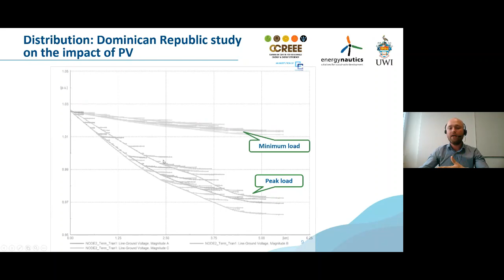When you integrate renewable energy or distributed energy, such as PV power plants, on such a feeder, you will have a declining voltage profile during peak load. You usually have a high voltage set point at the high voltage to medium voltage transformer, and over time, during minimum load, this voltage profile will not decrease as much. Even with some PV penetration, you can get a reverse power flow from the PV, which will increase your voltage.